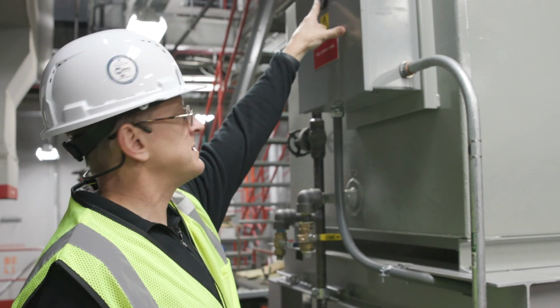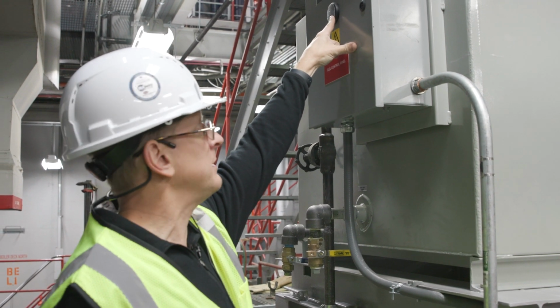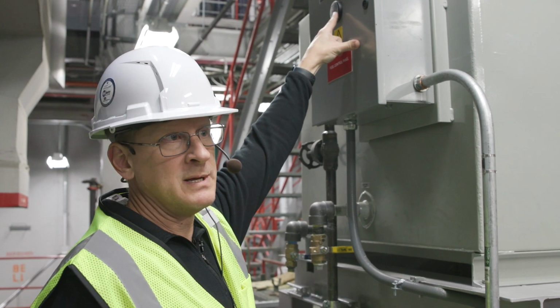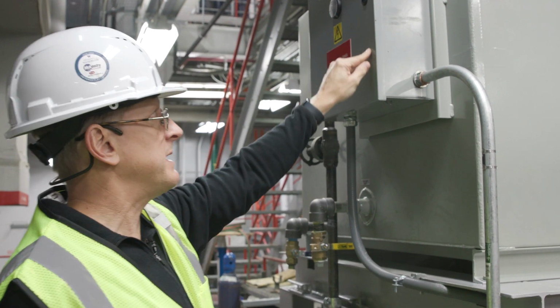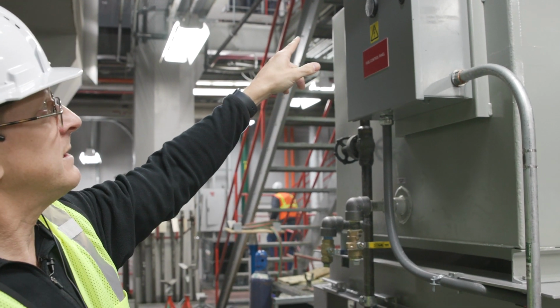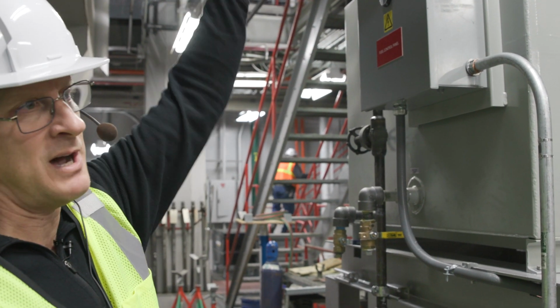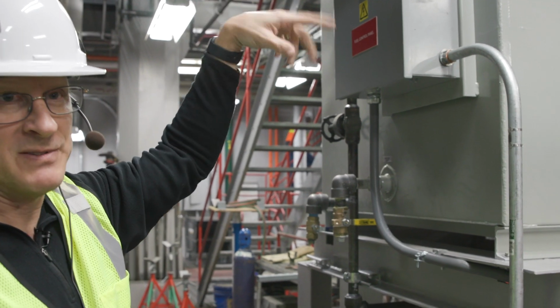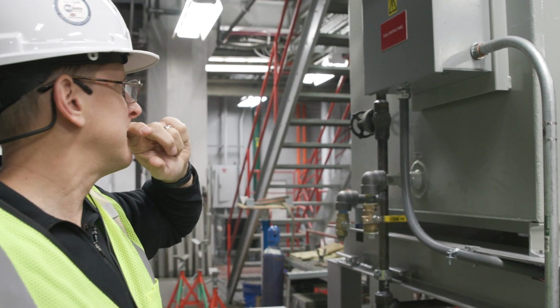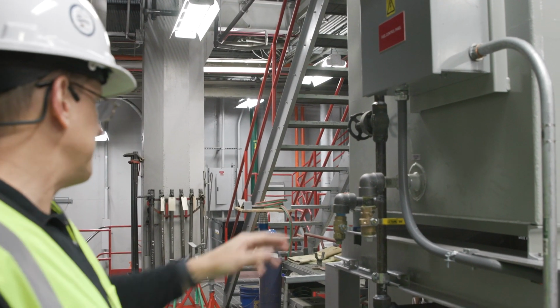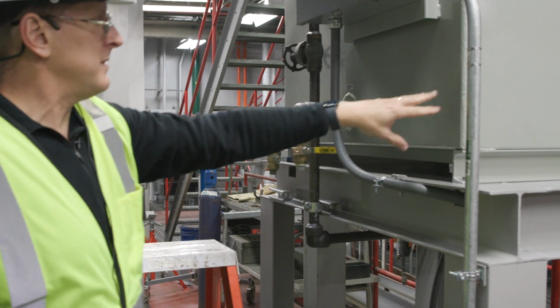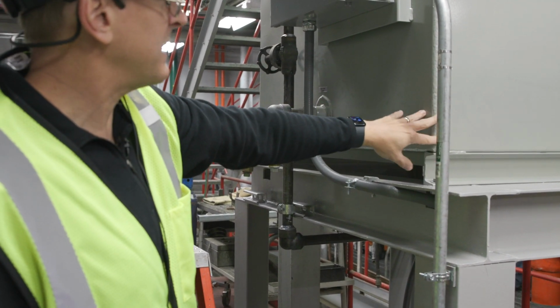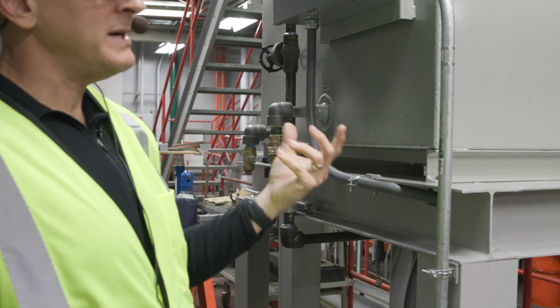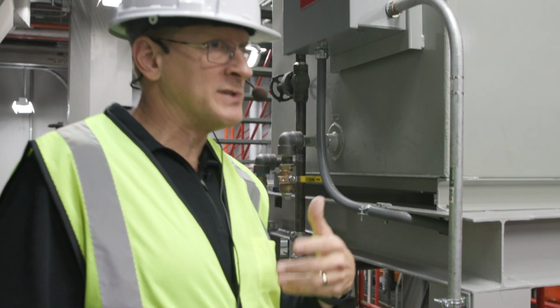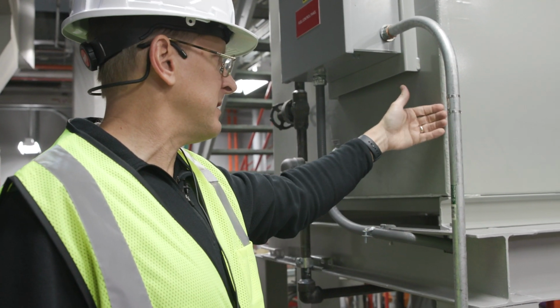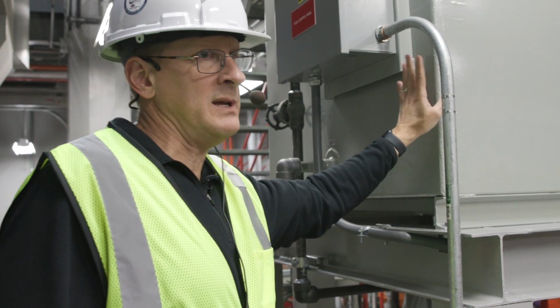The meter, the gauge that I mentioned to you that is not operable, is right on the front of the panel. We're going to put a power supply in here so that we can actually use that gauge, but there is a gauge on top of the day tank. You just have to get up on a ladder to look at it. Got drains for the main tank and for the secondary tank. Obviously, being a UL-142, if there happens to be a leak in the tank itself, it ruptures, it'll all be contained within the secondary tank.